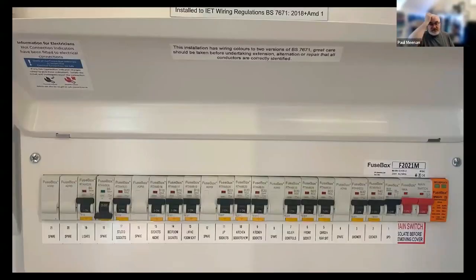Now, this is my favorite picture of all time. It's my fuse board downstairs, and that is what I call a minimal viable product. It is a fuse box, a very witty pun from the manufacturer. It's actually a consumer unit. And what I have there is my installation. It's a 21-way board, and I've labeled it all up. Each one of those devices, except for the surge, is an RCBO. So if there is a fault on the boiler controls, it only trips that. Sockets externally. So I have the added protection of an MCB and an RCD for every way, and I have surge protection. So that's a standard board. That's probably about £100 for the board plus the devices themselves.